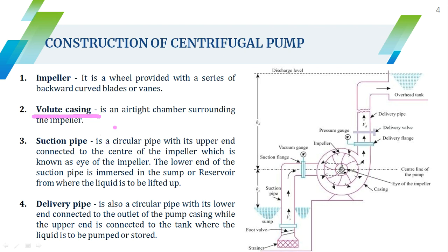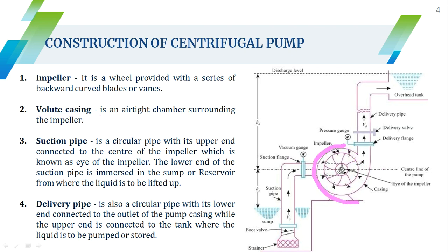The next part is the volute casing, which is an airtight chamber surrounding the impeller. The volute casing has an increasing cross-sectional area — at the beginning the area is small, and it increases as you move forward. Because of this increasing area, the velocity of the water gradually decreases, and when velocity decreases, pressure increases. That is why the volute casing has increasing area.